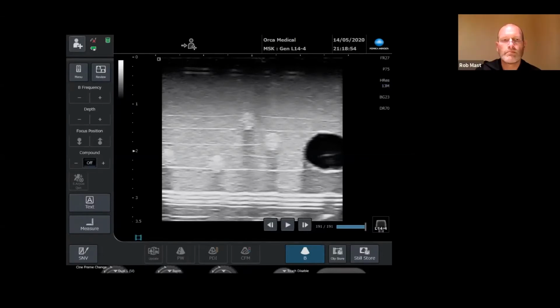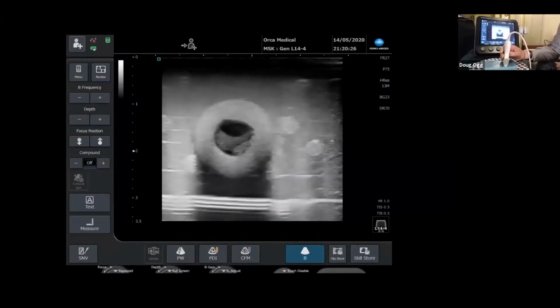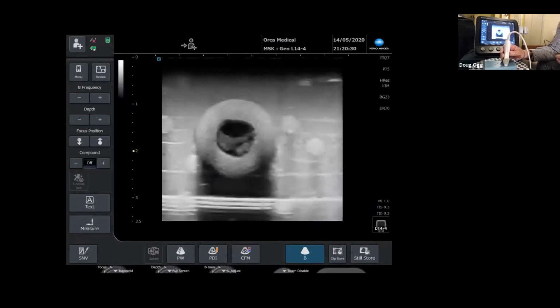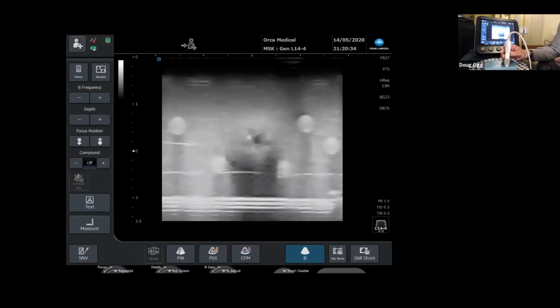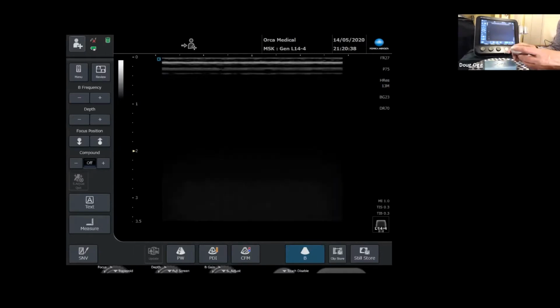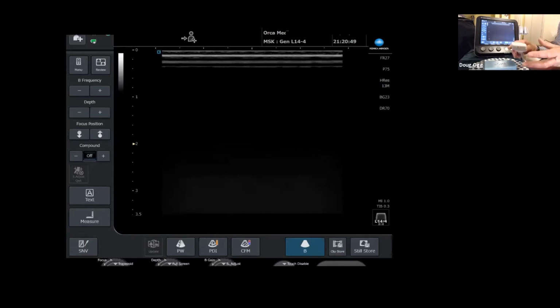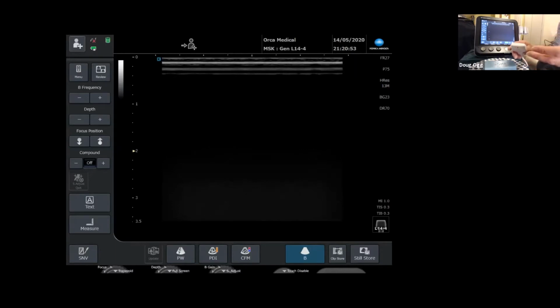Yeah. So do you want to talk us through a quick little test that people can do in their clinics, Doug? One of the things people always talk about with ultrasound probes is, oh, I've dropped the probe, better check to see if there's any dropout. In other words, damage to the face of the transducer, where the transducer material itself is a ceramic. As a ceramic, it can break, it can crack, and when it cracks, it'll lose the ability to transmit ultrasound. I've got a little paper clip here that I've just straightened to create a sort of thin wire.